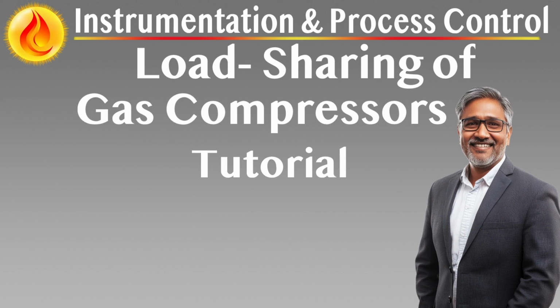the anti-surge controller, UIC, which prevents individual compressor surging through precise recycle control. Integrated control zones: hot recycle, per compressor surge mitigation. Cold recycle, network-wide thermal balancing using shared loops and a centralized heat exchanger. Loop decoupling avoids interaction delays by locally isolating performance, surge, and pressure feedback.